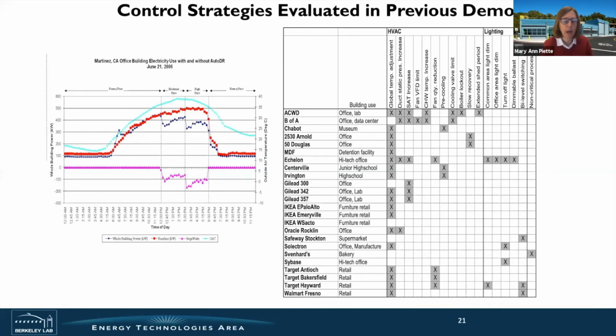They actually bought extra pans and turned off the dishwasher, so they choose what to do. These were all fully automated. We installed a gateway box with OpenADR, and used the existing control system to program strategies to allow the building to change its sequence of operations during the demand response events.